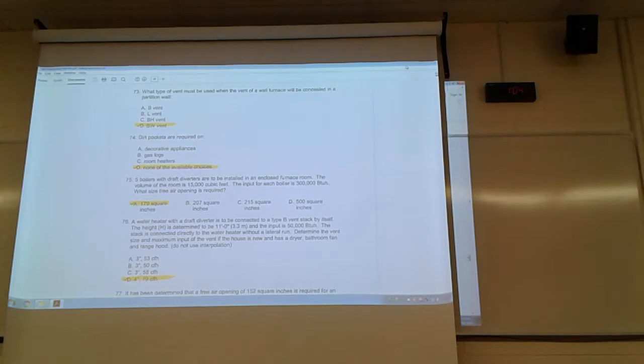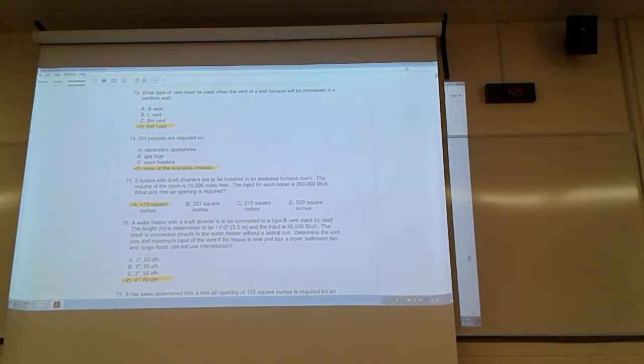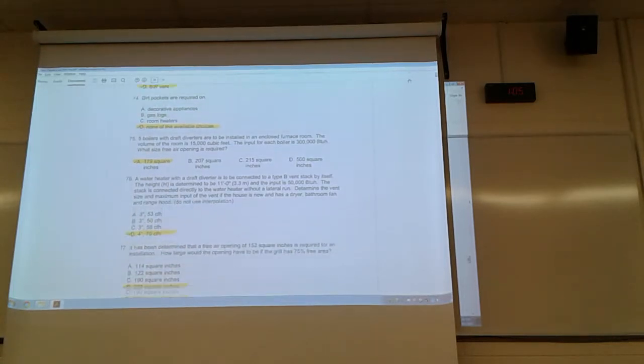Okay, what size of combustion air opening is required? So that's over 400,000 BTUs. Okay, so you've got 5 boilers and they are 300,000 BTU each. It doesn't matter what the cubic foot of the room is, you still need an opening to the outside. Everybody good with that? So over 400,000. You all have draft diverters, so you just go 5 times 300,000. For the first million, it is divided by 7,000 BTUs. For the remaining BTU, it is divided by 14,000. Add them together. Okay, 76.